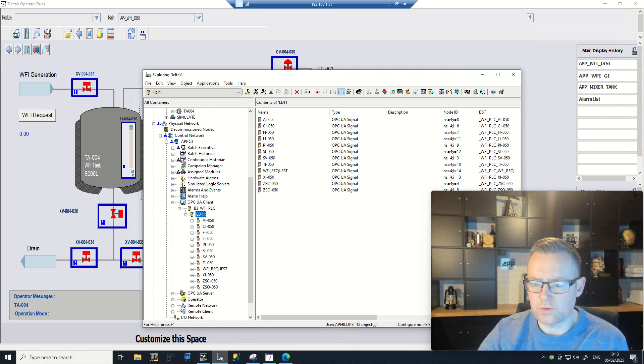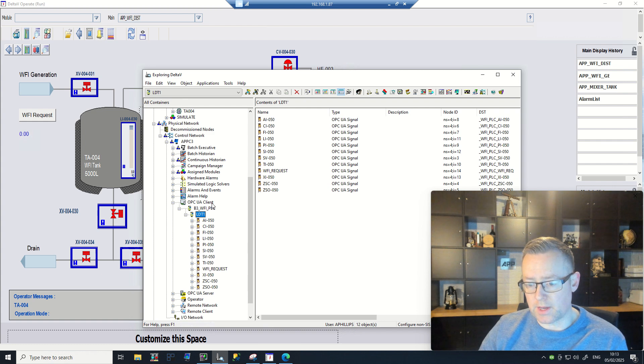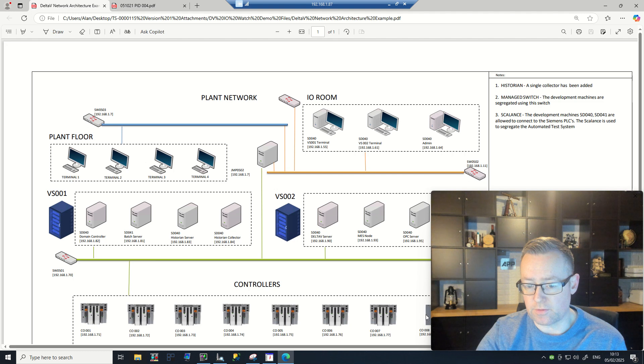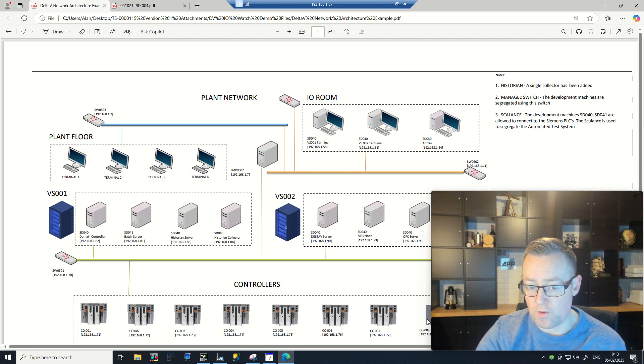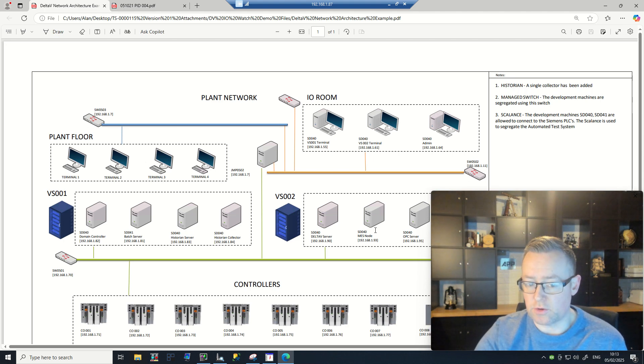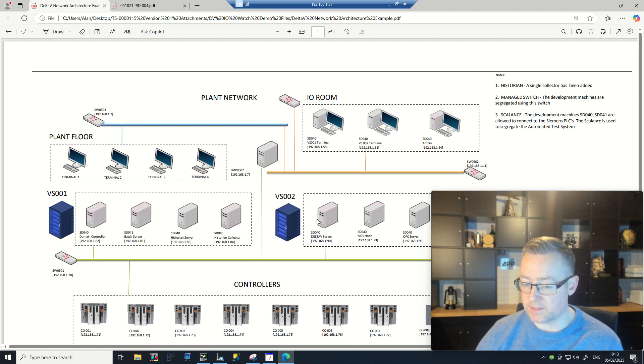In this video, I'm going to run through how to use the OPC UA client in Delta V to directly communicate to the OPC UA server on a Siemens PLC. This effectively means that in many scenarios, say for example with a Siemens PLC, communication normally has to go through an OPC server, which then relays the signals back to the Delta V system.